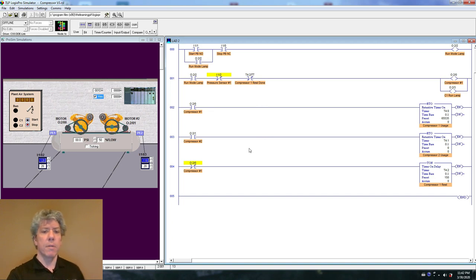Now let's think that through. If timer 2 is not running, which would be the case when we first start the program, then the compressor can come on. The only problem is that the compressor is going to shut off actually at the very beginning. This won't allow my compressors to come on very quickly, but that might be okay. Let's think through it. The compressors initially would be off when the program first starts. So that would make the timer start running.